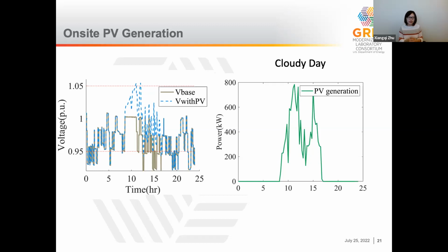Therefore, it is important to design appropriate sizes for the 3 critical parts: the PV, the storage, and the charger, in a smart charging solution, so it can balance the reactive power and the real power, and balance out the fluctuation of the PV generation. In this way, the energy storage can effectively store excess PV power and power the charging load when PV is not generating, and the inverter can provide enough reactive power support when there is not enough on-site real power generation.